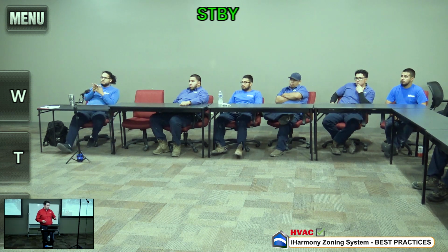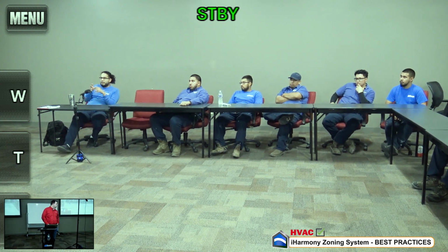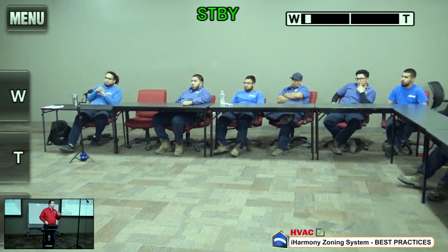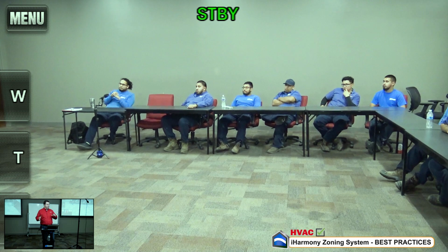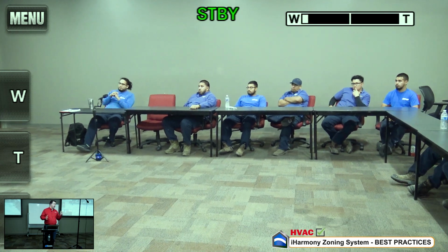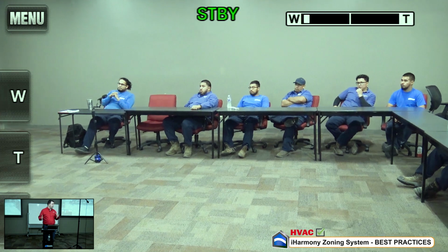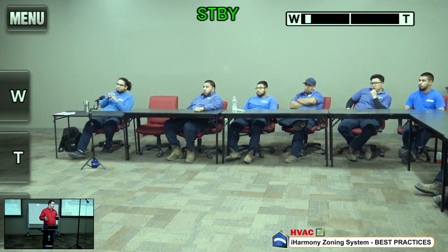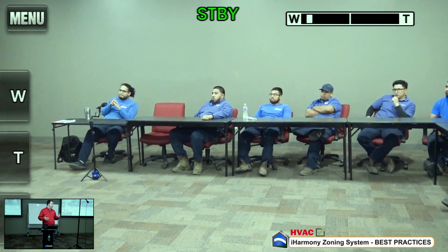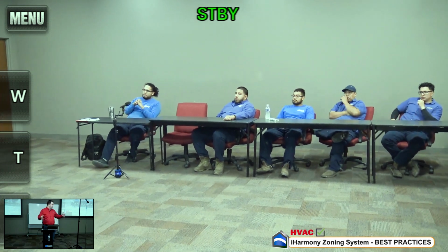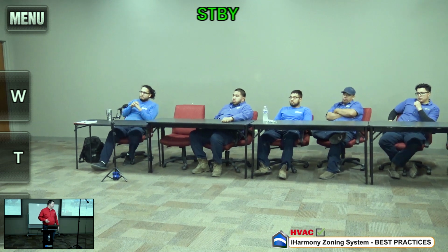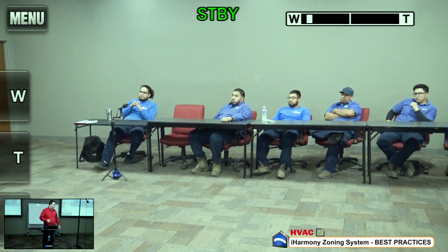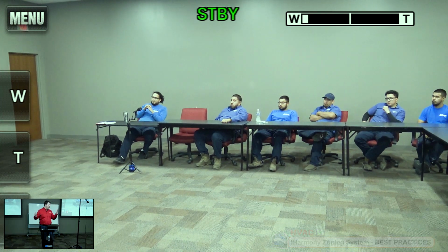So what if I'm charging a condenser on a cool day, so the house is kind of cool inside already? How would I go about charging it if it keeps killing it off that sensor? Well, that's kind of a separate issue, because if you're in a low ambient situation, a lot of these systems are going to have built-in low ambient operation. But if that becomes an issue, I would just block the coil off with a plastic bag. That would be just as you would with anything else in low ambient operation.